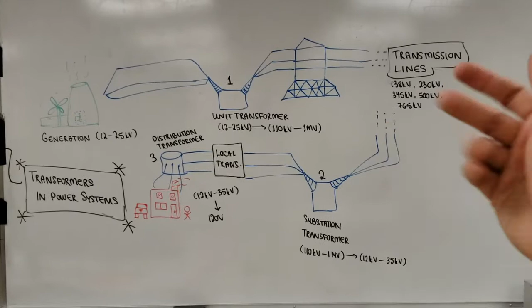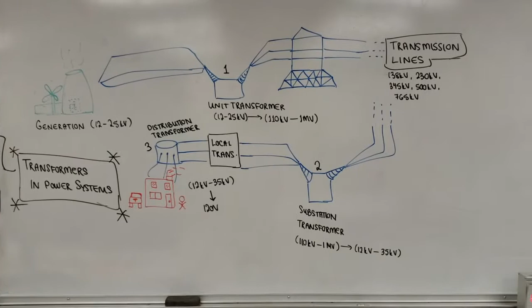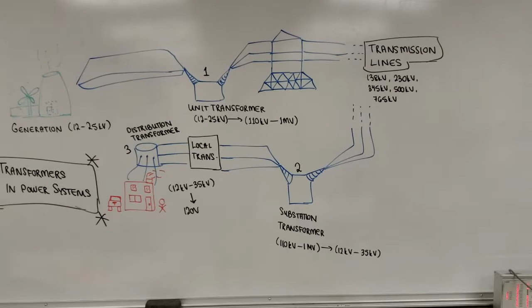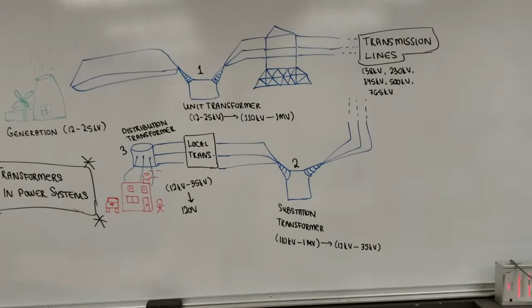As you can see in this basic system diagram of a power system, you have generation that occurs at 12 to 25 kilovolts. This is where some form of other energy is converted to electrical energy - usually mechanical energy drives turbines, which drive the generator, which creates electrical energy - and then a unit transformer right after. This unit transformer is the first transformer encountered in this system.